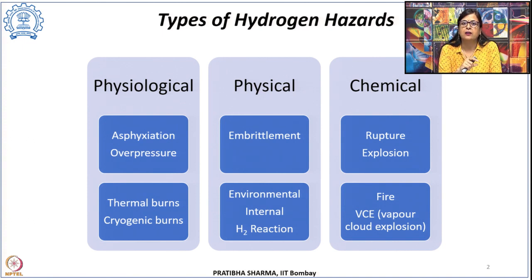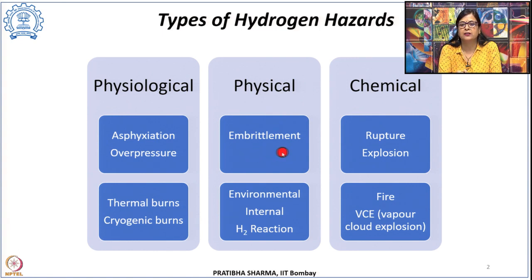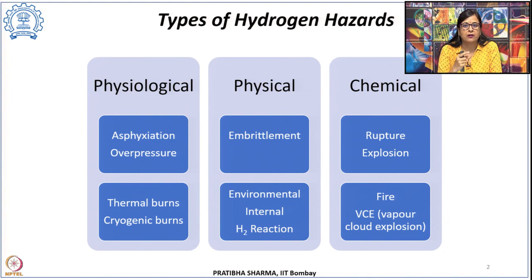There can be cryogenic burns when the skin comes in contact with cold or cryogenic fluids, leading to cryogenic burns, frostbite, or even hypothermia. There could be physical hazards, which are primarily because of embrittlement — the change in mechanical properties that can lead to failure, rupture, or leakage from different materials. There could also be chemical hazards because of chemical reactions with the material, or oxidation and combustion of the hydrogen-air mixture leading to fire, tank rupture, or vapor cloud explosions.